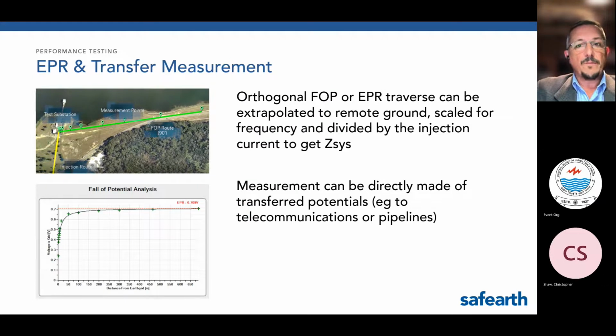So we've got a simulated fault passing current. Now measurements can be taken of transfer voltages. And we can do a voltage traverse by starting at the station and measuring the voltage at distances away. If you see in the bottom left there, a graph of the light green line at the top. As you move further away from the station, the voltage you're measuring is showing you an increase, which is the inverse of the EPR of the station. So we can use fall of potential tests to accurately determine the earth potential rise, even in an energized station.